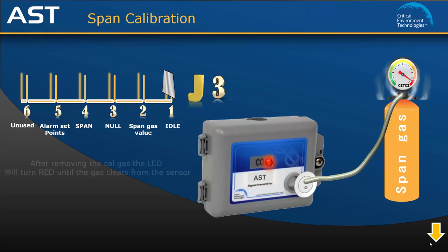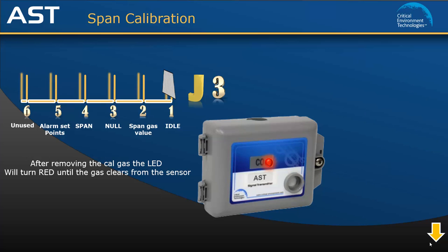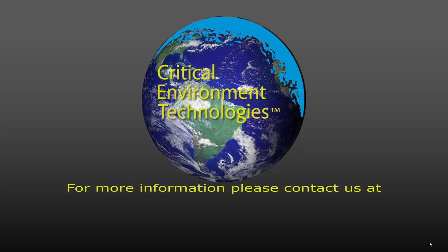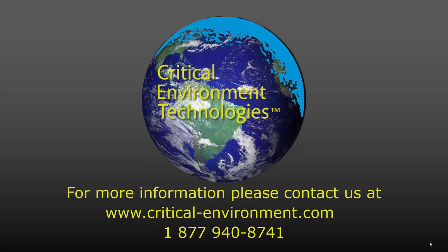The LED light will turn red because the sensor is sensing residual gas. As the gas dissipates, the LED will turn amber and then green. This completes the calibration procedure for the AST 2nd Generation Analog Transmitter. If you would like more information, please visit us at critical-environment.com or contact your authorized dealer, regional sales manager, or any other member of our team at 1-877-940-8741.